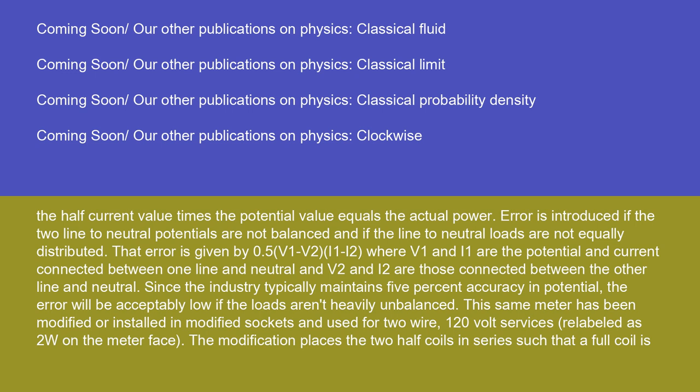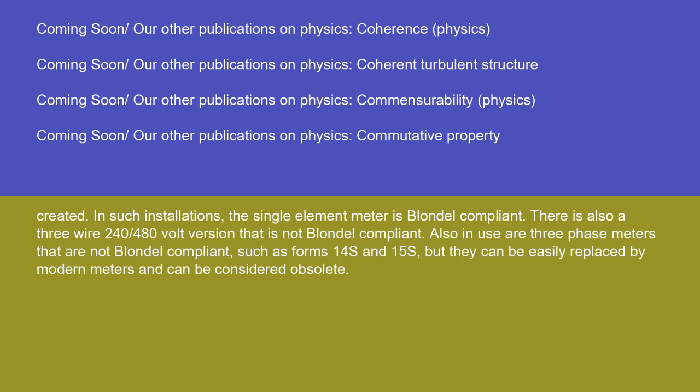This same meter has been modified or installed in modified sockets and used for two-wire 120-volt services, relabeled as 2W on the meter face. The modification places the two half-coils in series such that a full coil is created, and in such installations the single-element meter is Blondel compliant. There is also a three-wire 240/480-volt version that is not Blondel compliant. Also in use are three-phase meters that are not Blondel compliant, such as Forms 14S and 15S, but they can be easily replaced by modern meters and can be considered obsolete.